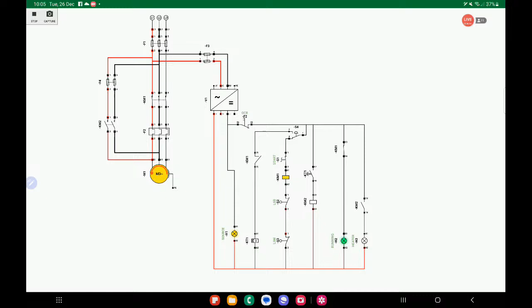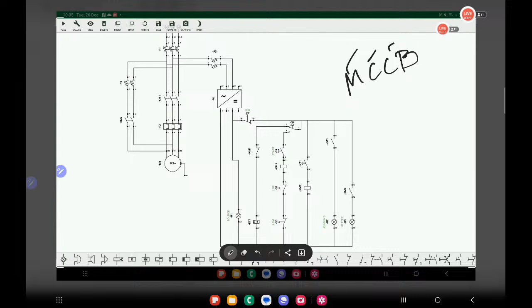Speaking of emergency stops, the best design for emergency stop is that those emergency stops will activate the shunt trip coil of each MCCB. MCCB stands for molded case circuit breaker. Main protection is overloading and short circuit. And then they have this shunt trip coil built with them, that once we press, it will activate the F1, or it will trip the F1. So once F1 is tripped, that will be the main function of the emergency stop.